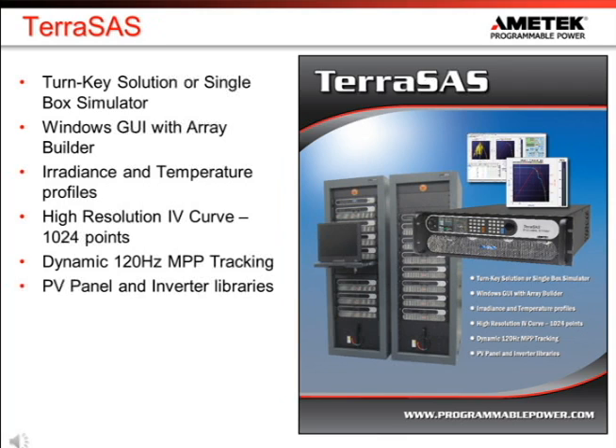Both systems share Windows graphical user interfaces with array builders, irradiance and temperature profiles pre-programmed, and high-resolution IV curves with 1024 points. This is essential in developing good MPP tracking algorithms. Dynamic 120Hz MPP tracking capability means this system is good for both microinverters and string inverters. Finally, both systems offer access to online libraries for both panels and inverters.